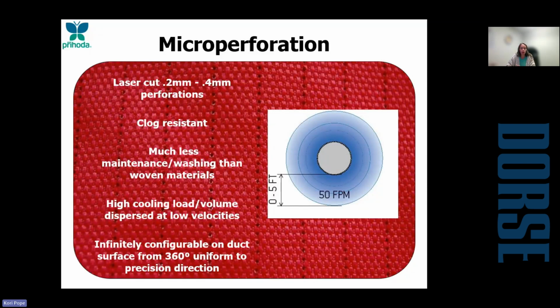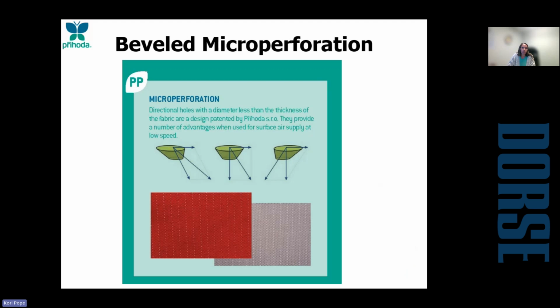The first one I'm going to talk on is our micro perforations. This is what we would use ideally for putting a lot of air into a room at extremely low velocities. So your classrooms, any type of labs, offices, anything like that with a lower ceiling, this is what we would recommend. This is a bunch of tiny laser cut holes that can be located at any orientation on the duct with as many or as few rows as are needed. When we're going in with the laser cutter to make the micro perforations, we can also adjust how that laser is creating the hole in the material itself, and in a sense, bevel that micro perforation. This just gives us a little more control of where that air is going to be blowing into the room.